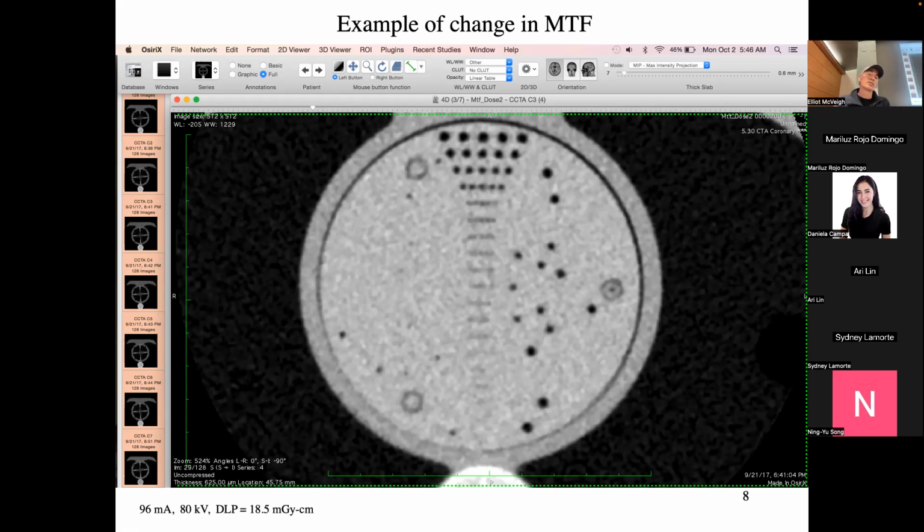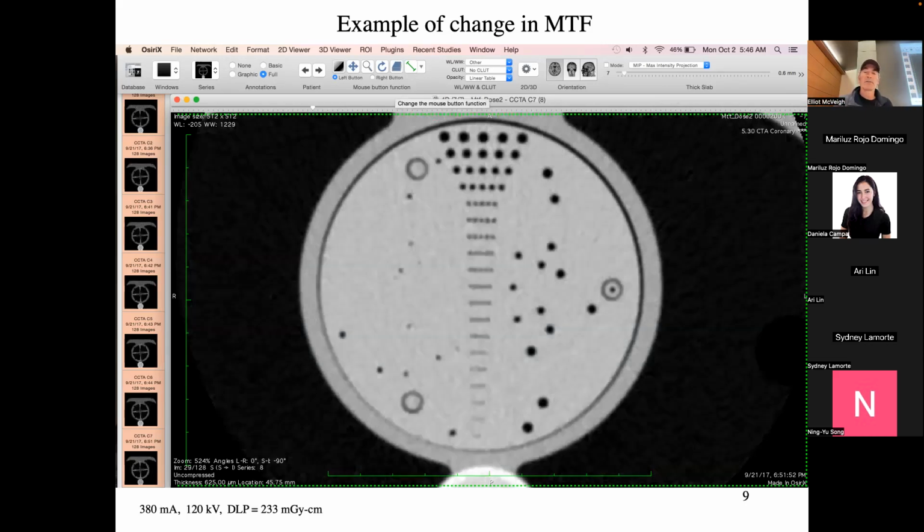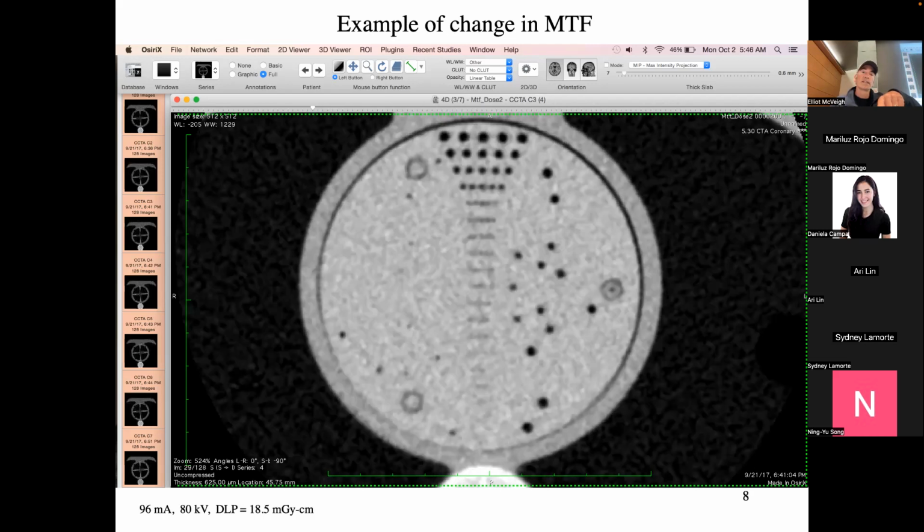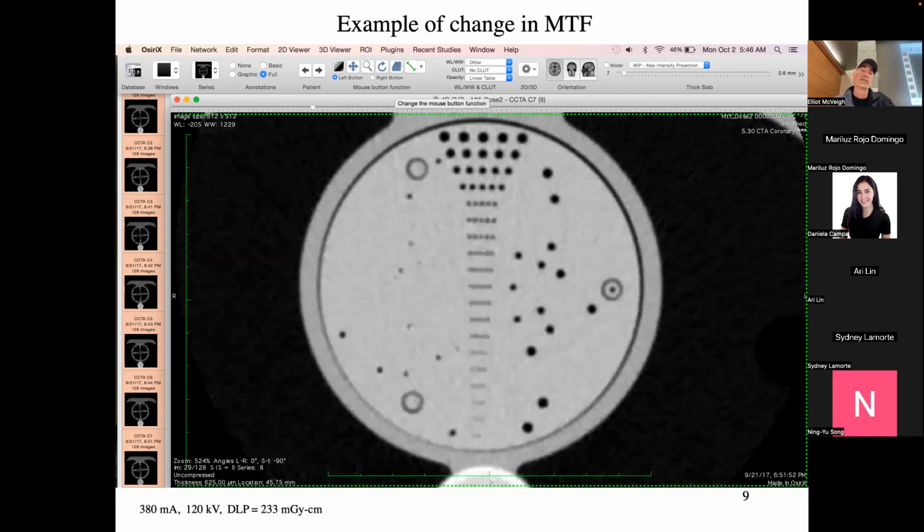This is an image obtained with a minimum amount of X-ray radiation. So we'll say it's 50 milliamps going through the tube or something like that. And then when you turn that up, it turns into this. If we increase the number of X-rays, we get this picture. Decrease, we get this picture, okay? Two things are happening. In the background, there's higher noise here than there is here, okay?